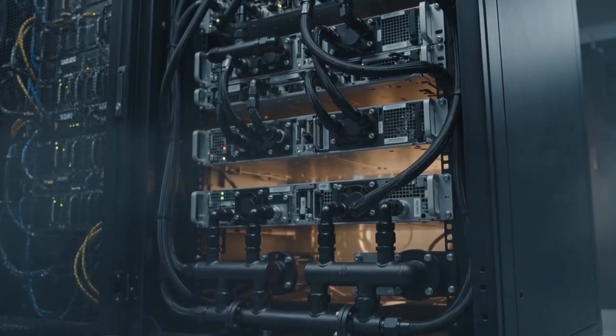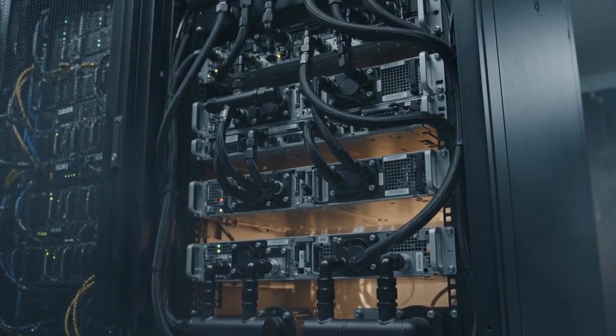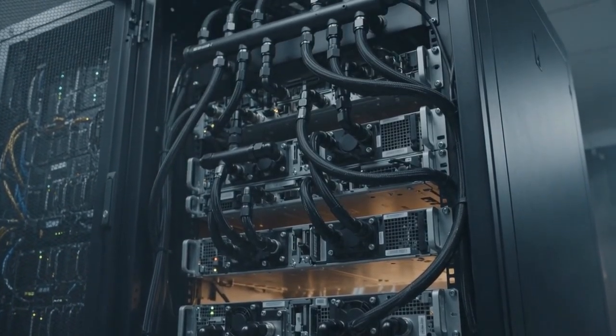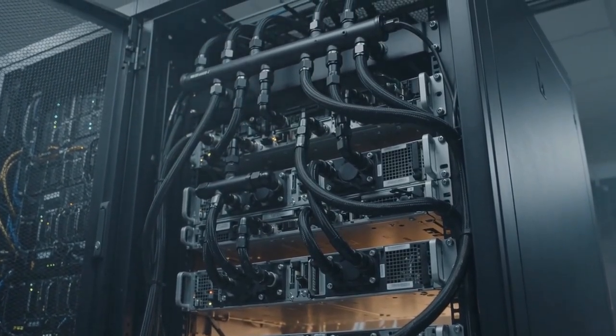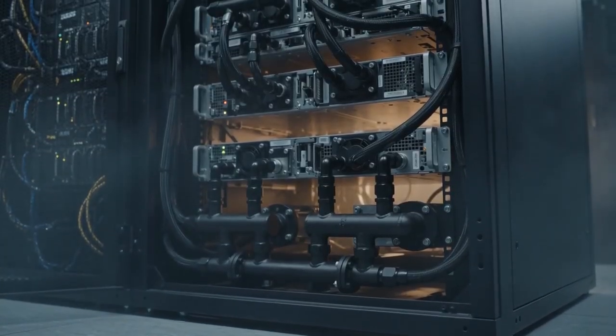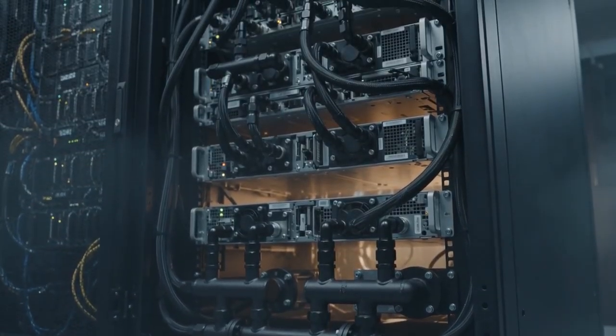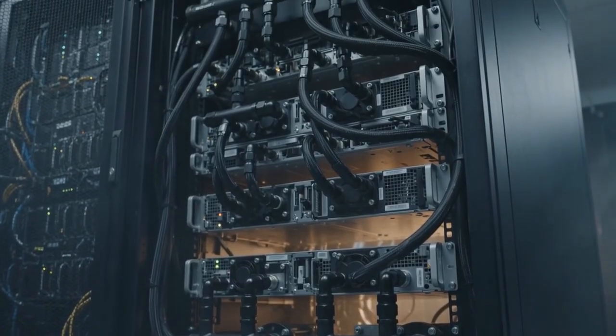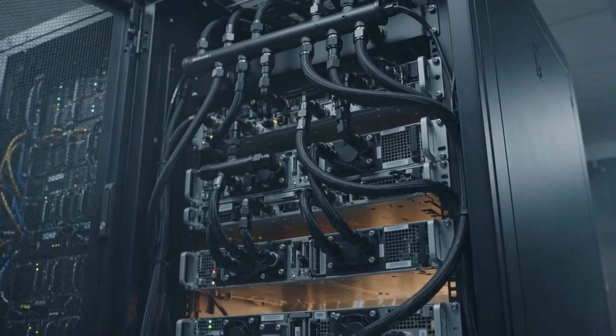The current flagship AI rack wires 72 GPUs into one unit, drawing around 120 kilowatts, roughly 10 times a conventional rack. It weighs about 1.5 tons. Floors have to be reinforced. Power systems have to be redesigned.